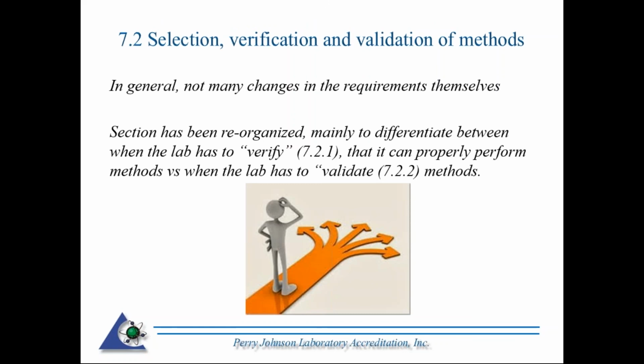Okay, moving on to section 7.2, selection, verification, and validation of methods. Basically, this section is still intact from 2005. It is, however, reorganized to differentiate between when the lab has to verify, which is captured under 7.2.1, and when it has to validate, which is captured under 7.2.2.